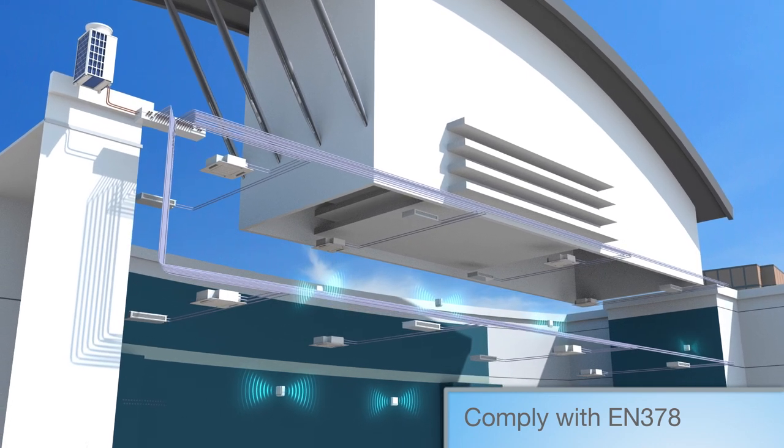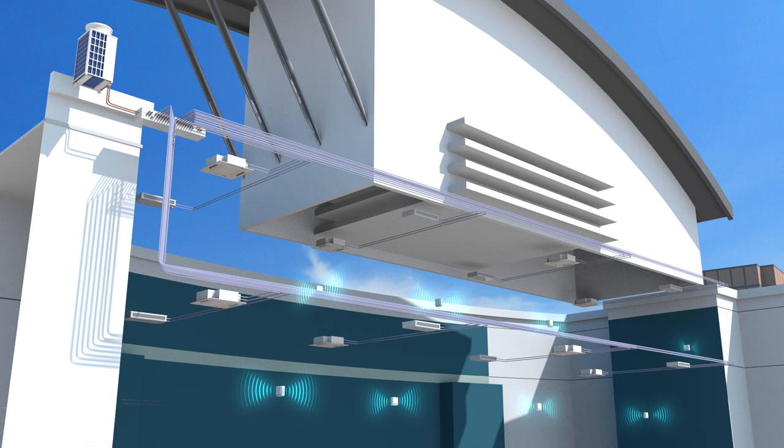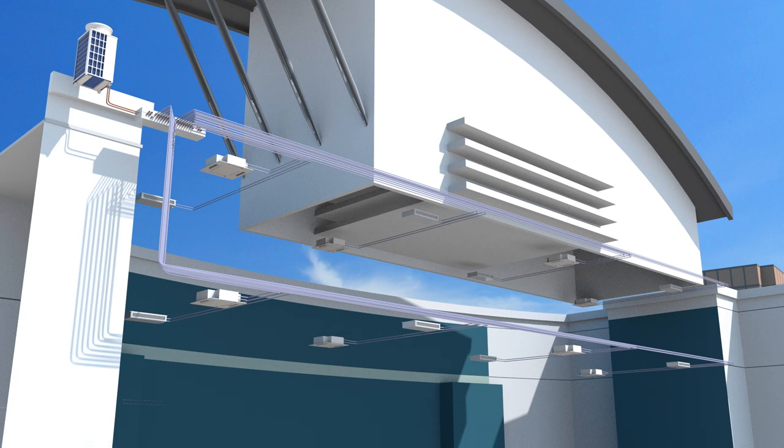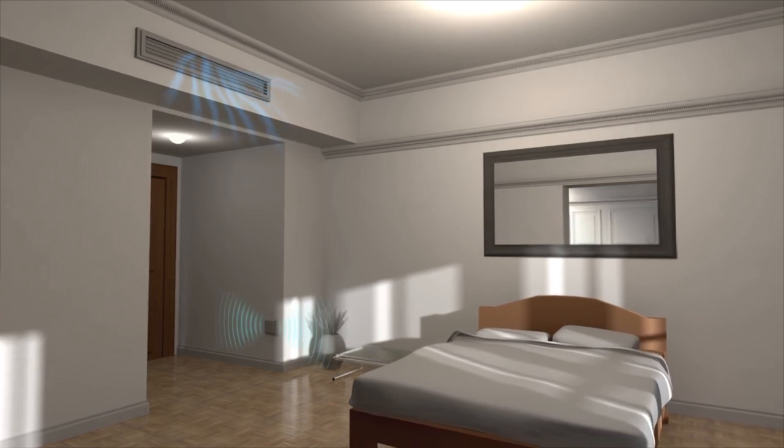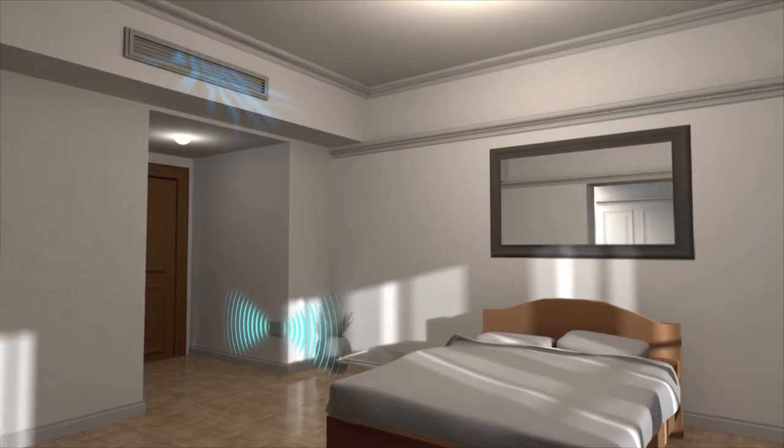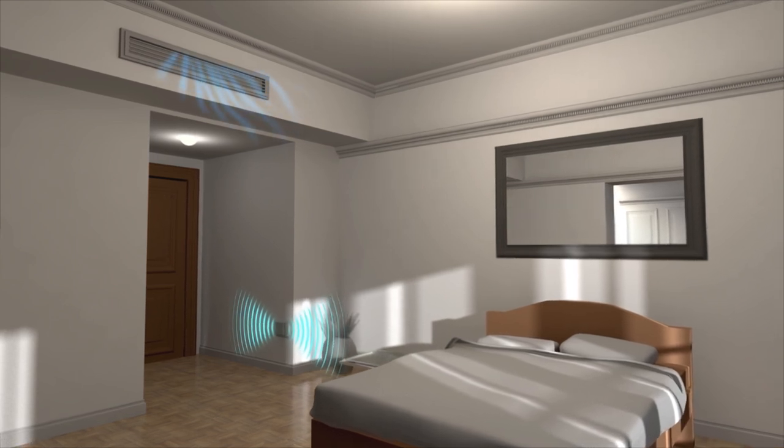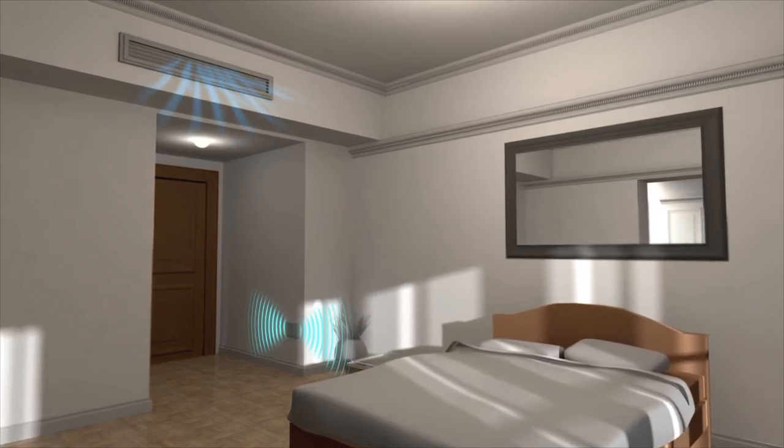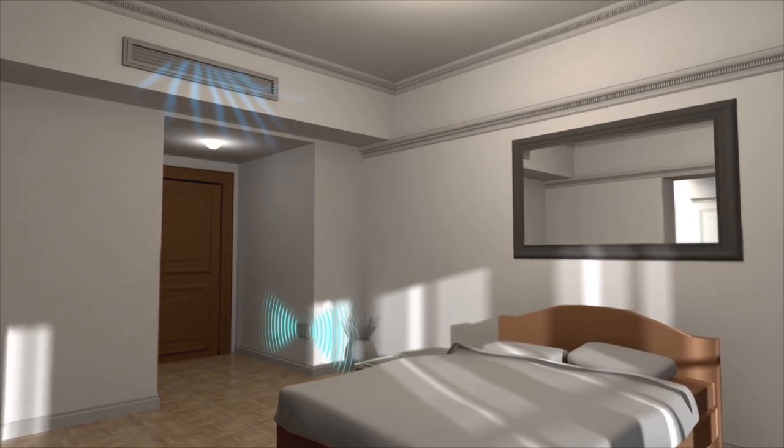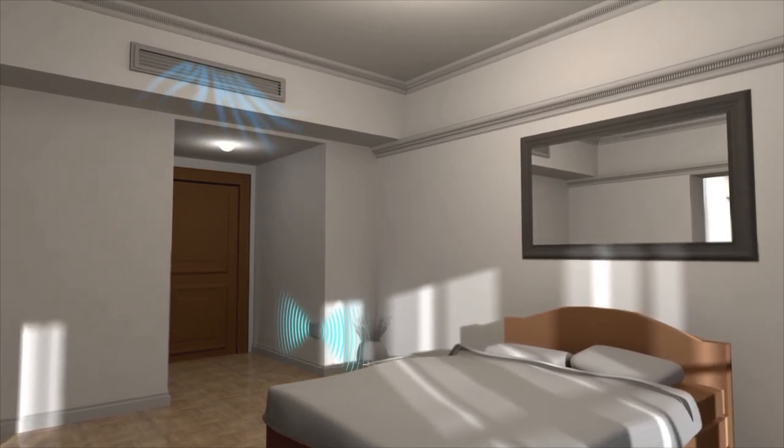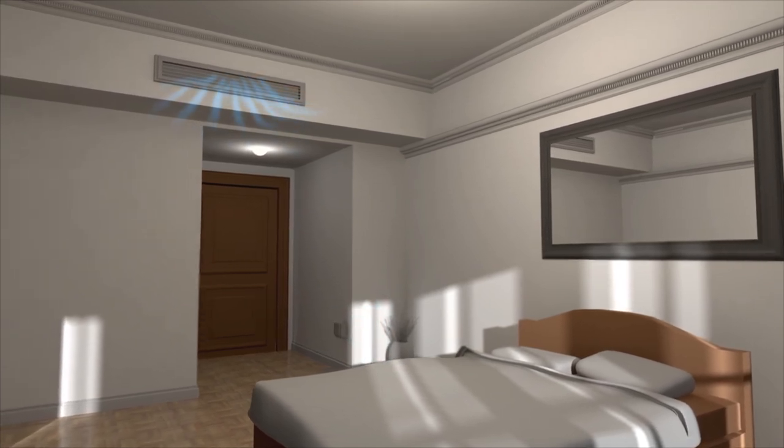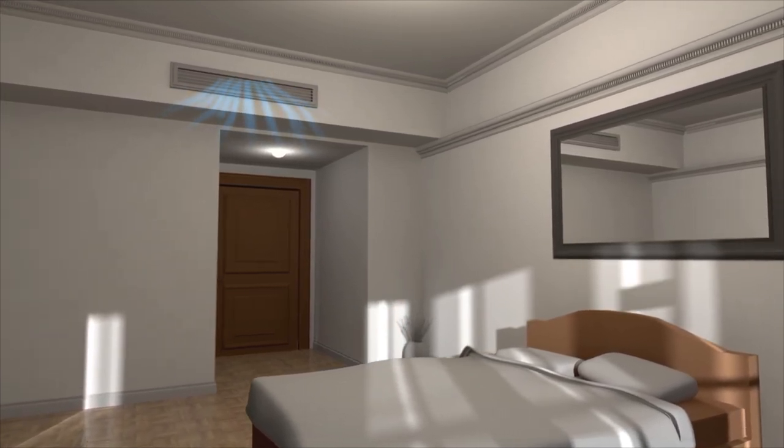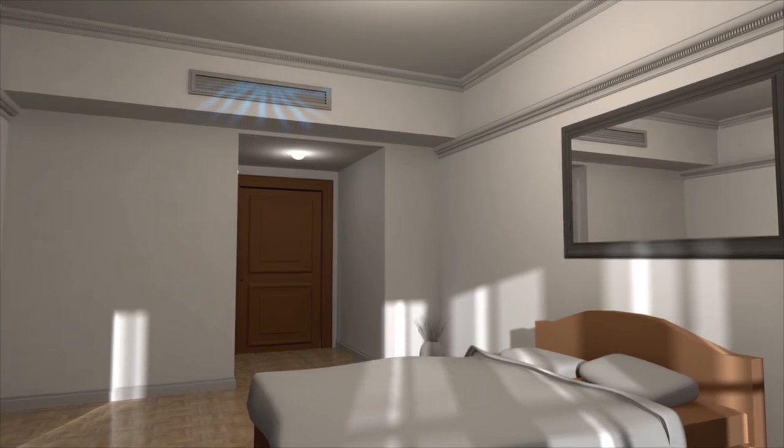but allowing the building to comply with refrigerant legislation such as EN 378. This makes hybrid VRF ideal for all situations, where the use of refrigerant would otherwise call for the additional cost and installation of leak detection equipment. Not only is this important in the office sector, but in modern hotels it is now an essential requirement. So hybrid VRF means any building can now benefit from advanced air conditioning and perfect comfort control, without the need for leak detection equipment.